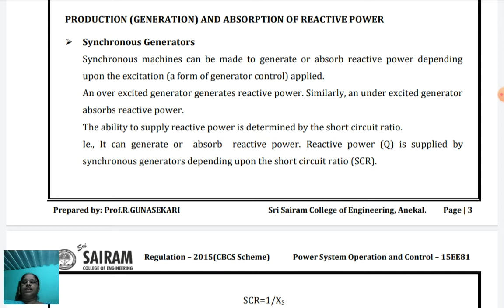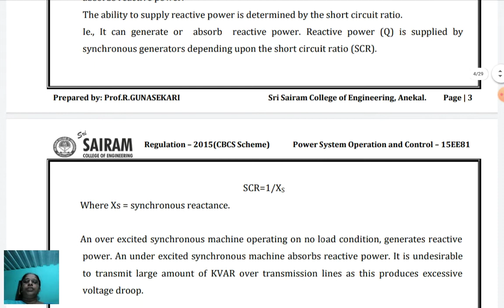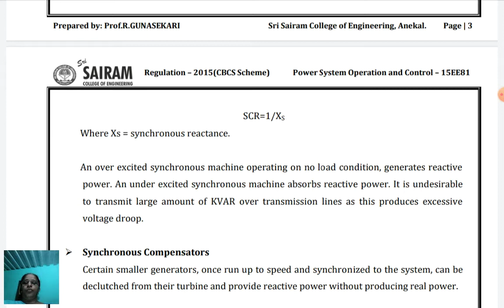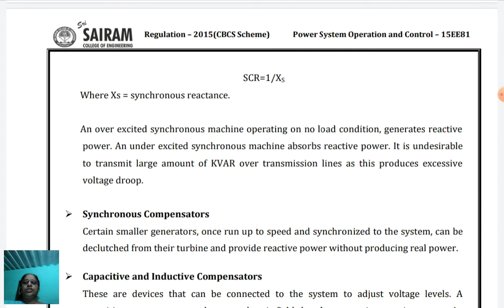The ability to supply reactive power is determined by the short circuit ratio. That means the generator can generate or absorb reactive power depending upon the short circuit ratio. The short circuit ratio, SCR, is equal to the reciprocal of the synchronous reactance. An over-excited synchronous machine operating at no load generates reactive power. An under-excited synchronous machine absorbs reactive power. So it is undesirable to transmit a large amount of kVA over a transmission line, as this produces excessive voltage drop.